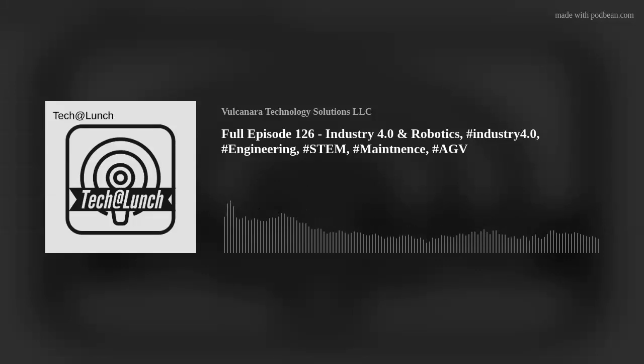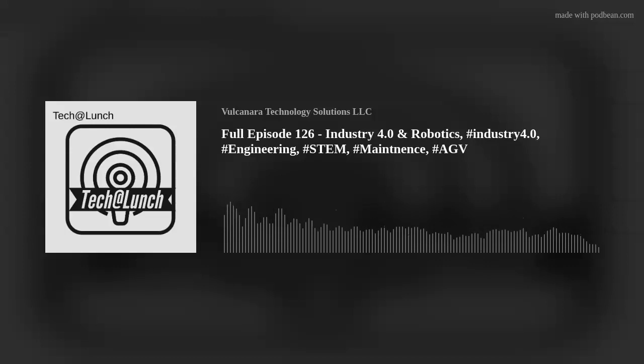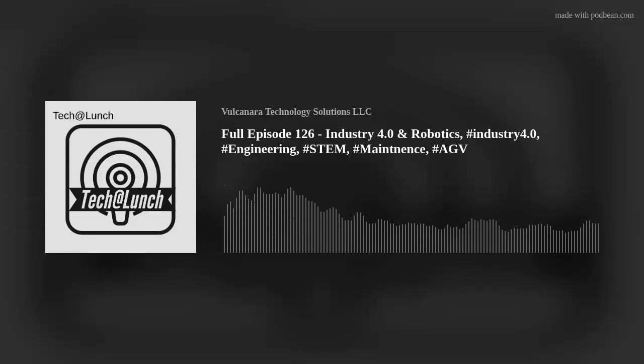But what I'm thinking is, when we start seeing this type of stuff, we are running a SCADA, or some sort of version thereof. Say you have countdown clocks on your maintenance ERP system, right? Every cycle count of an actuator or something like that will send a message via MQTT through the SCADA into the ERP system and activate that countdown clock. Every cycle knocks down one. Then you can have real-time dashboards telling you what your maintenance schedule is looking like. It says, okay, I am 5 days away from having to do a valve PM, or I'm 6 days away from this, based on cycle count. And that can also be done on. Normally, we don't necessarily do it on cycle. Yeah.